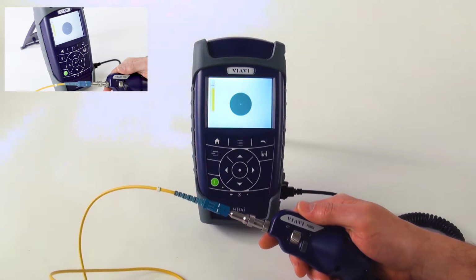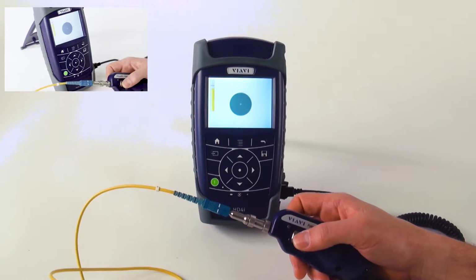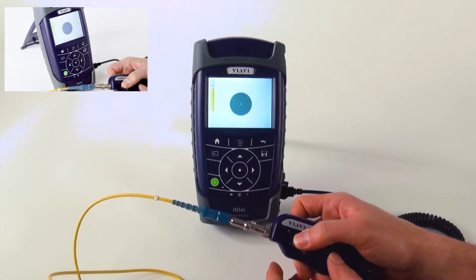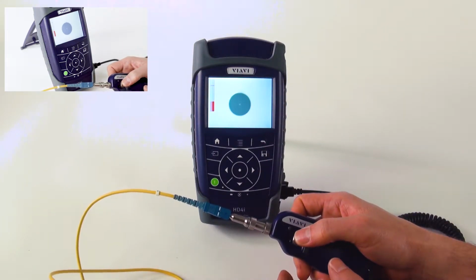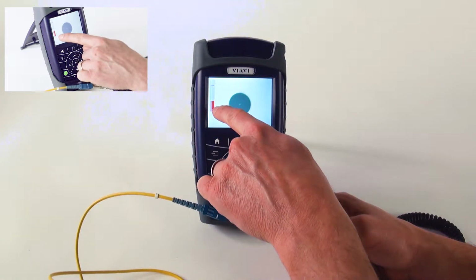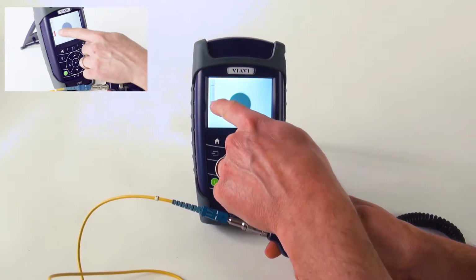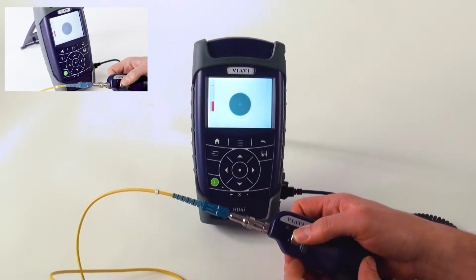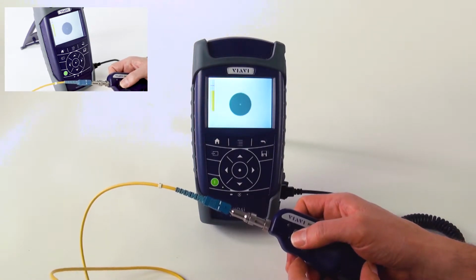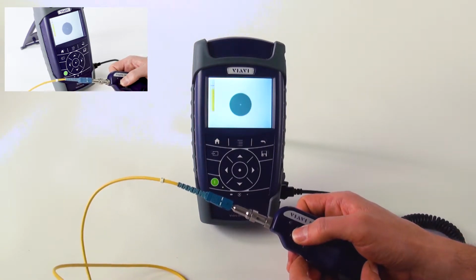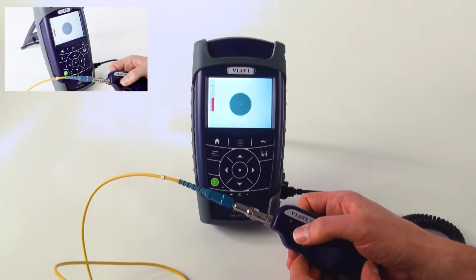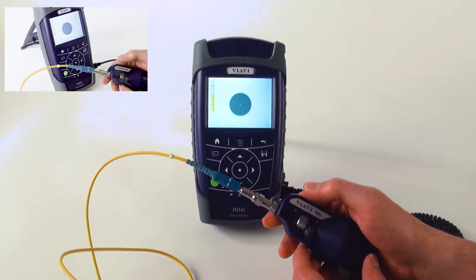Now that I have all my acceptance criteria set up, I'm ready to go ahead and proceed forward with testing. Now you can see on the screen here that the image is in fairly good focus. I'm going to get that out of focus for a bit, and you can see that the focus quality meter goes down and it indicates a red color, which tells me that's not in a good enough state to be able to be running a test. So I'll get that in focus here, and I can proceed forward.